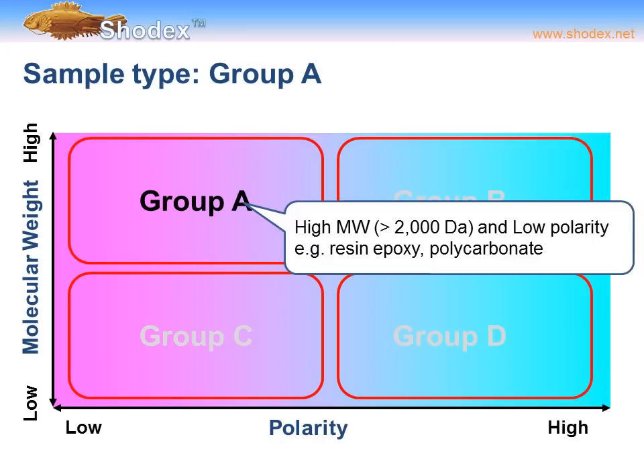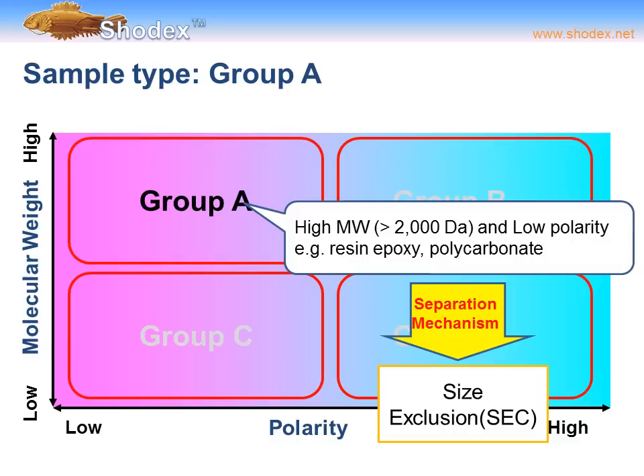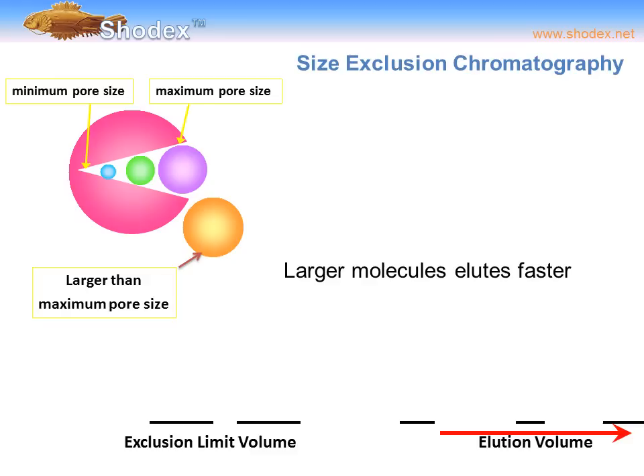These sample groups help us determine which type of separation is best. For group A — high molecular weight, low polarity — typical examples include resin epoxy and polycarbonate. These are polymers with very low polarity. The best separation mechanism is size exclusion chromatography, often abbreviated SEC.